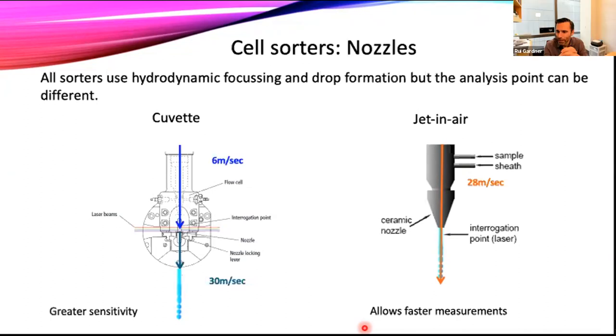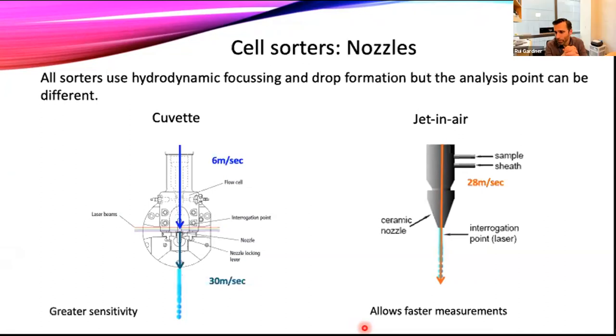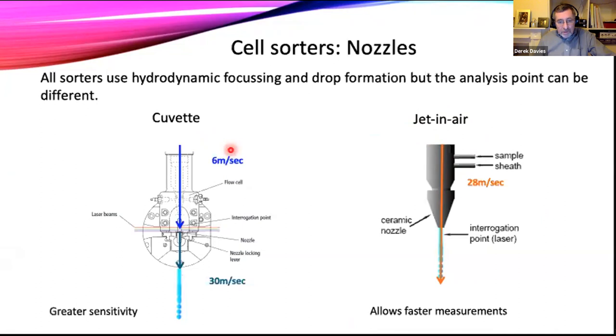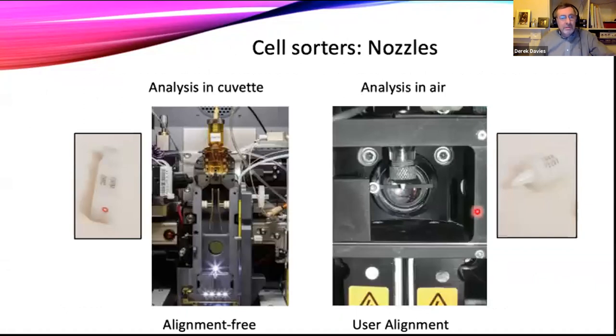Question: how are charges deposited on droplets in a four-way sort? It's exactly the same way as in a one-way sort — you just vary the charge. The cytometer decides which way you want particular populations to go: it gives the biggest charge to the population going to the left, a slightly lower charge of the same polarity to another population going left, and does the same on the right-hand side. Adam's follow-up: where is the piezoelectric crystal? It's basically above the flow cell — slightly different on different cytometers — sending that sound wave through the stream.